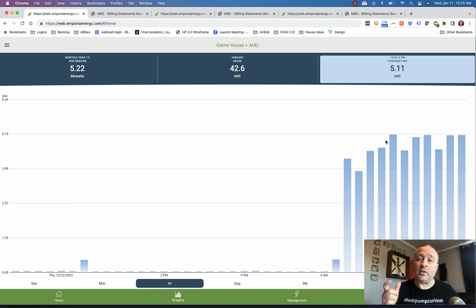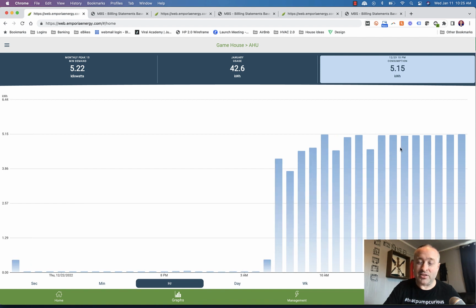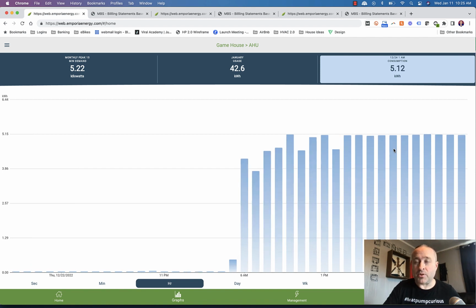It got pretty cold here. So design temperature here is 11 degrees, which means 99% of the year we are above 11. We got down to just below 0 here. And so this is beyond design. So technically, the temperature is allowed to slide. It's easy enough to usually have a little extra resistance to prevent that from happening. But I needed the resistance and the heat pump to be able to hold temperature. And I only had resistance in this case.